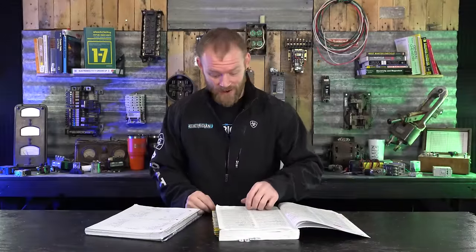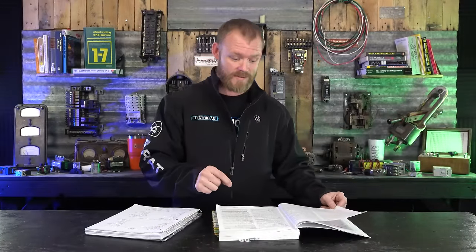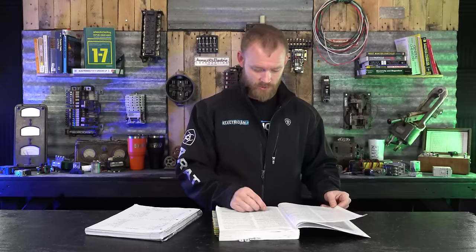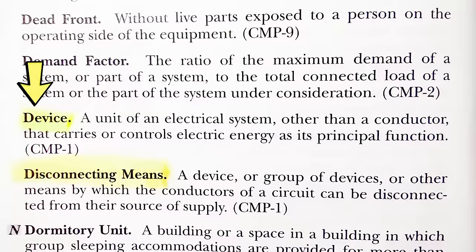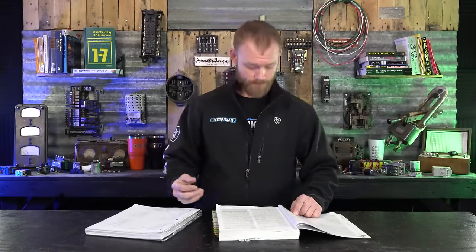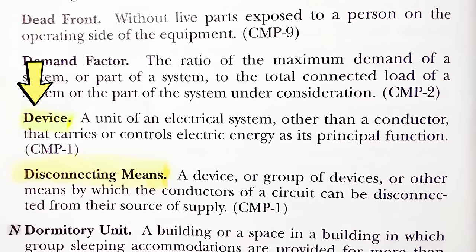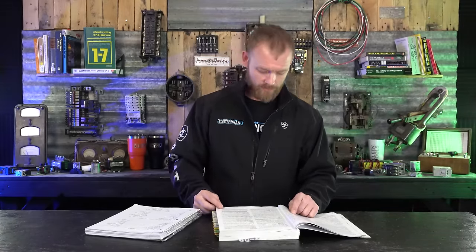Then lastly, we have device. So how does it delineate the difference between a device and appliance or utilization equipment? A device is a unit of an electrical system. So now we're talking about things that are on the premises wiring system, not things that get plugged into it or hooked up to it. It's other than a conductor, so we don't consider conductors devices, and that carries or controls electric energy as its principal function. So it doesn't only mean it's receptacles or switches, but it does mean it's something that as its principal function has current flowing through it. It carries that current and does some kind of function.